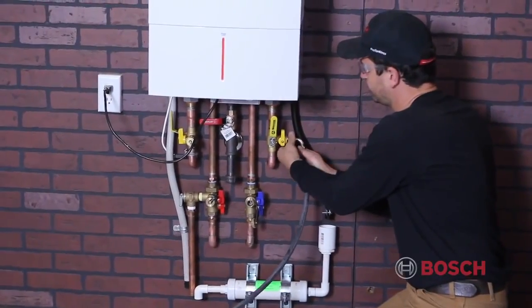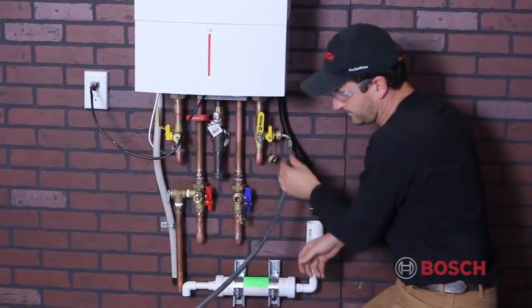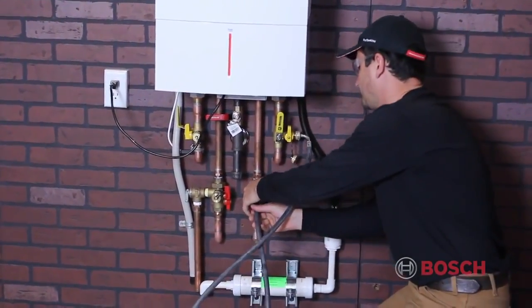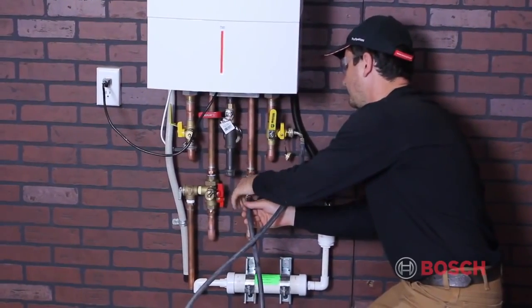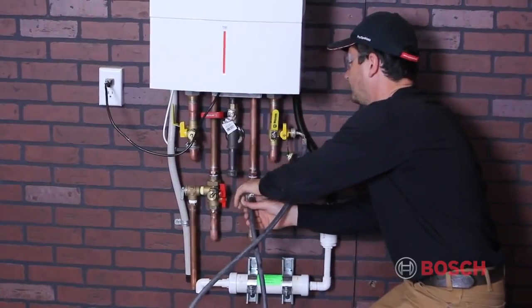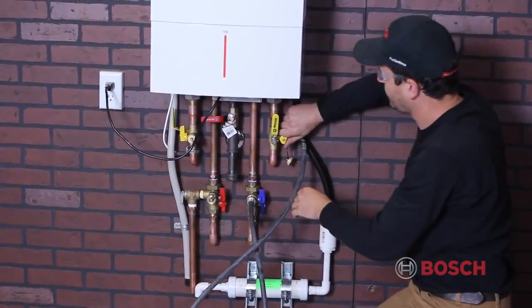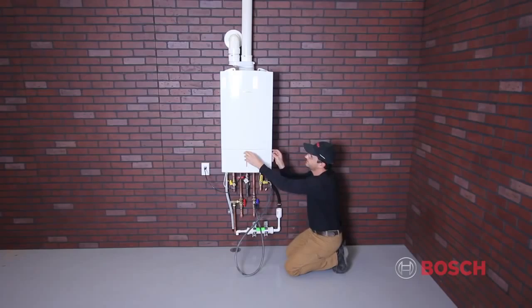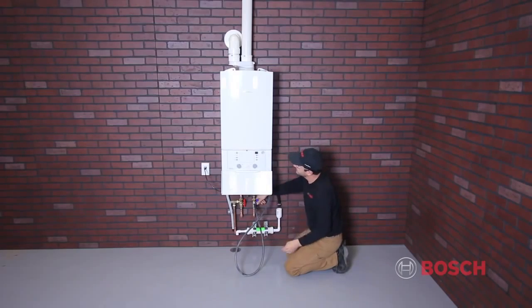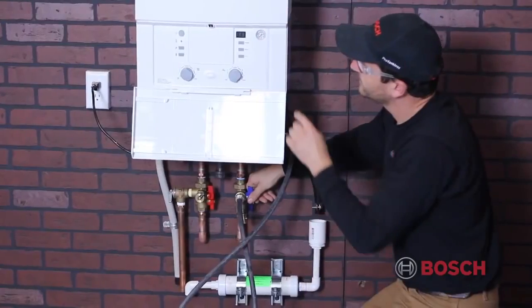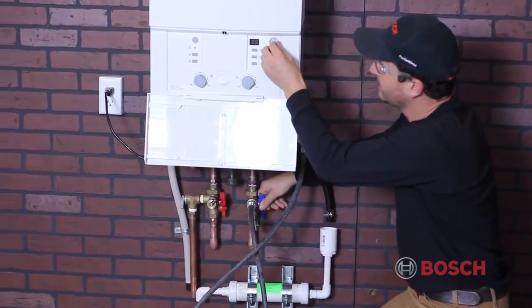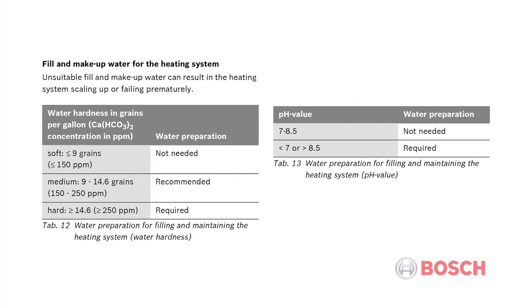The first step to commissioning your boiler is to determine your water supply and fill locations. In this installation, we've chosen to use the domestic cold water supply going into the flat plate heat exchanger and a fill location on the heating return side. Check your local codes to determine if a fill and backflow preventer is required. Please note that unsuitable fill and makeup water can result in the heating system scaling up or failing prematurely.